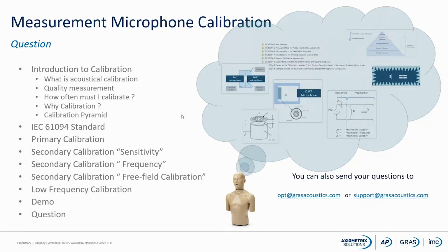There's one who's asking if I have a sound level meter, a calibrated sound level meter, should I still have a calibrated sound level calibrator to perform a daily check? I would actually recommend it, and the reason why is if you only have your calibrated sound level meter, and it's calibrated maybe once a year, then you don't know what is actually happening with your sound level meter as well as the microphone you have mounted on it over time. So therefore, I think it is a good idea to have a calibrator to know where you actually are. And I would also recommend that you have a yearly check of the sound calibrator.